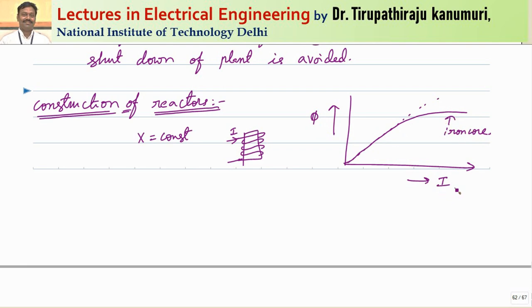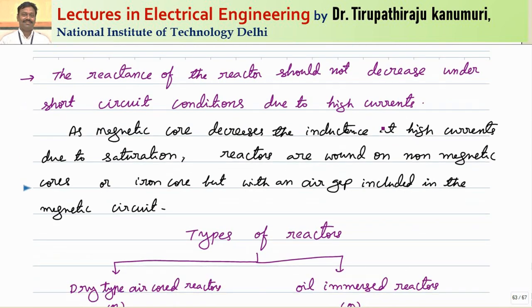Under fault conditions, the current drawn is extremely high, causing the core to saturate. As a result, the reactance of the reactor decreases — it is no longer constant. To maintain constant reactance, operation must be kept within the linear range, which requires a large core to avoid saturation. Therefore, reactors are either wound on non-magnetic cores, or if an iron core must be used, air gaps are included in the magnetic circuit.